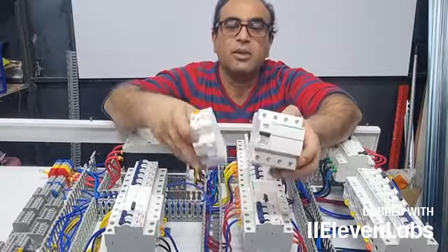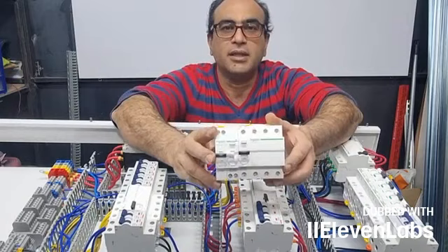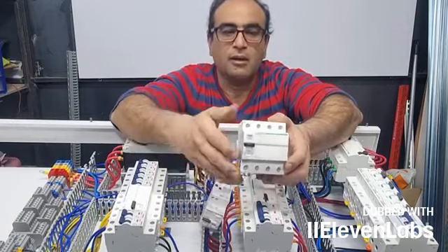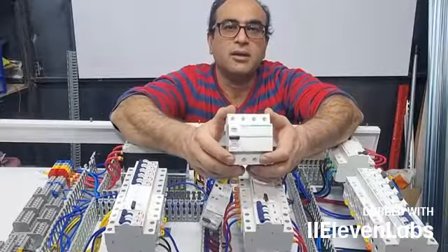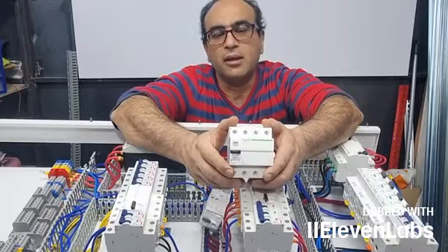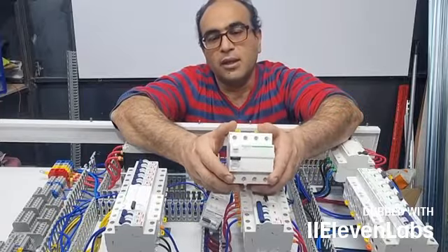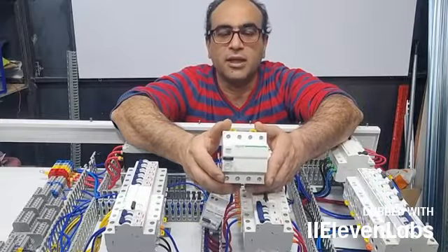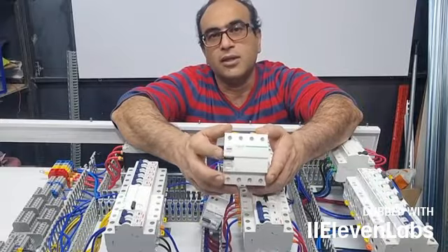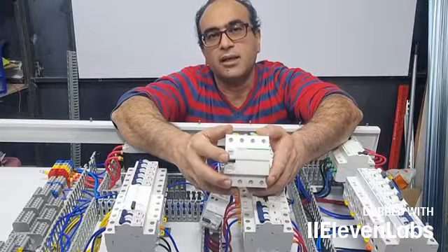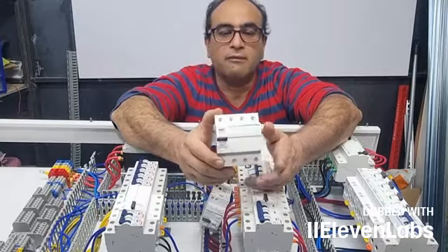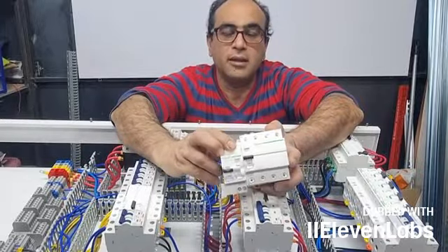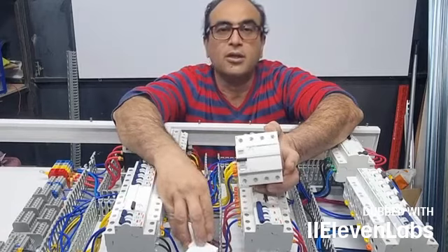And overall, these two parts are known as residual current devices or leakage current switches. And the leakage current up to 30 milliamps, meaning below 30 milliamps, might not be dangerous, but if it exceeds 30 milliamps, because you are at the threshold of getting an electric shock, the leakage current breaker detects it and cuts it off quickly. And these RCDs only operate if the earthing system has been implemented and its resistance is below 2 ohms.